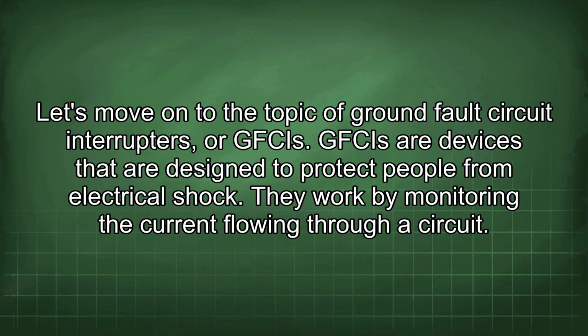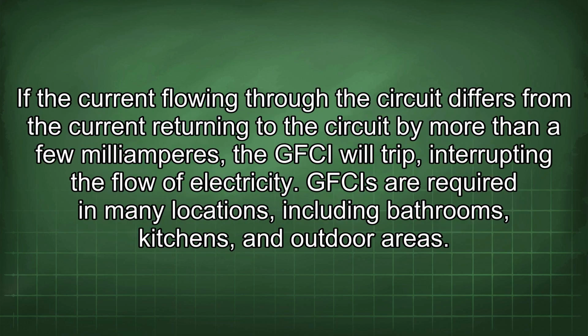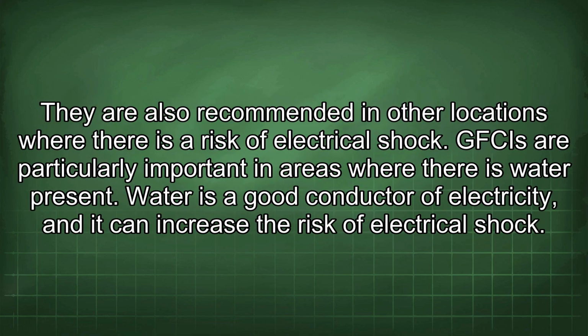Let's move on to the topic of ground fault circuit interrupters, or GFCIs. GFCIs are devices that are designed to protect people from electrical shock. They work by monitoring the current flowing through a circuit. If the current flowing through the circuit differs from the current returning to the circuit by more than a few milliamperes, the GFCI will trip, interrupting the flow of electricity. GFCIs are required in many locations, including bathrooms, kitchens, and outdoor areas. They are also recommended in other locations where there is a risk of electrical shock.